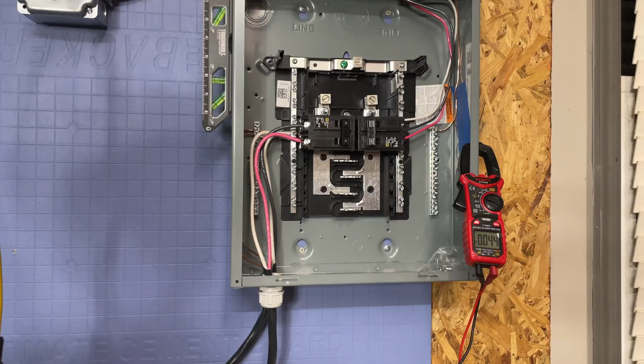This other black wire is the other inverter coming in. The neutrals go to the neutral bar, and the grounds go to the ground bars, and the hots connect to this 2-pole breaker. This breaker here is power going out, so don't worry about that one right now. Right now the neutrals are on one bus, the grounds are on another bus, and the ground-neutral bond is happening right here with that green bonding plug. A load panel will come with that, but in any system you really need just one spot to do the neutral and ground bond, and in this system it's happening right there.